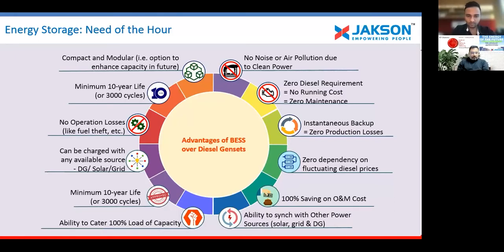For example, if we buy a DG set of 100 kVA, the block loading or step loading capacity is just 50 to 55%, and average loading is 70-75%. Whereas in BESS, 100 kilowatt means a 100 kilowatt single step load can be put on it without any derating.